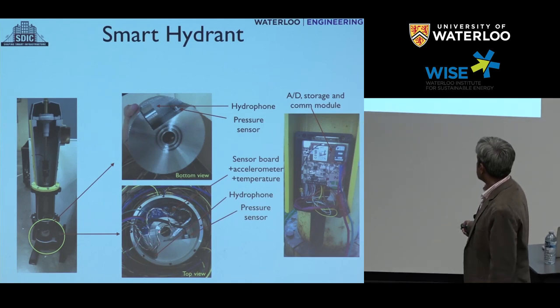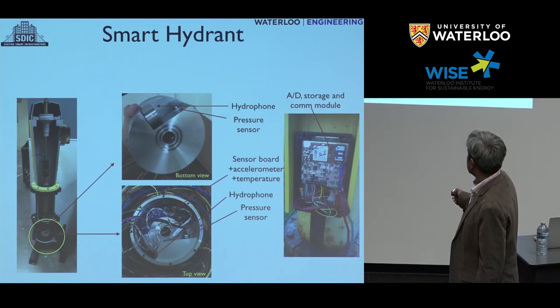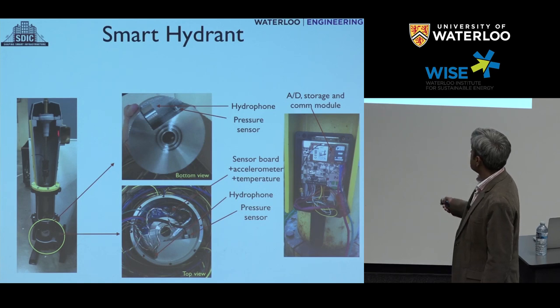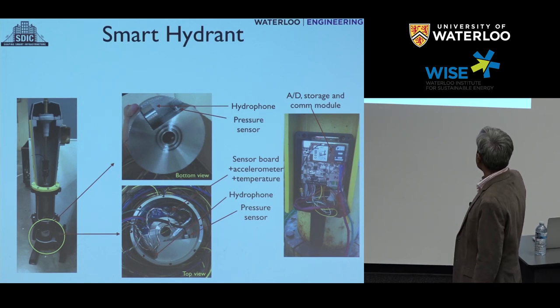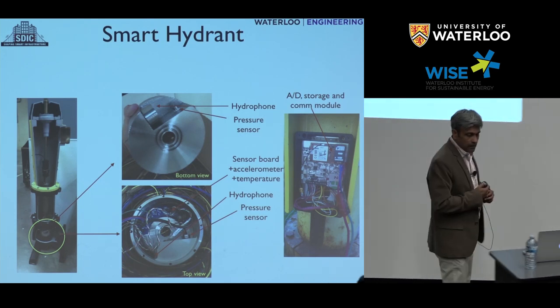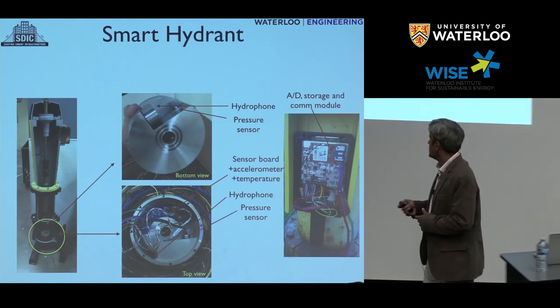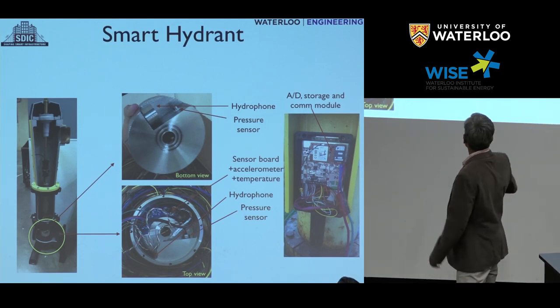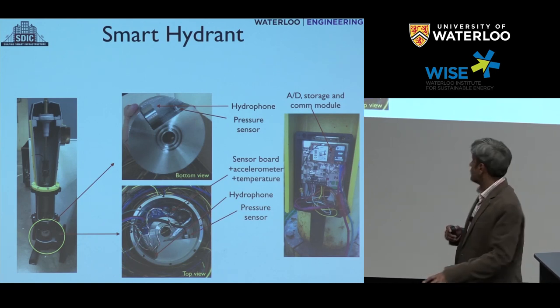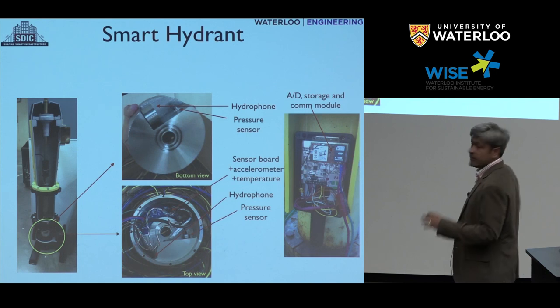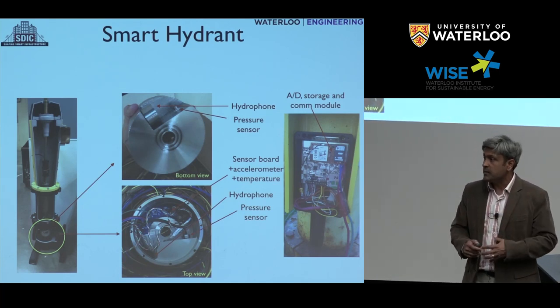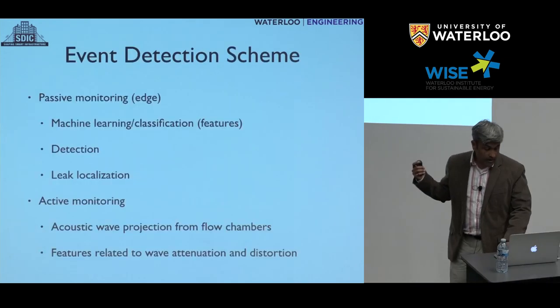Here are pictures of our hydrant in the hydraulics lab. The two sensors you can readily see are the hydrophone and the pressure sensor; there's also an accelerometer and temperature gauge. This gives a multi-sensor modality. The data is collected within the system and hauled back into the data acquisition unit — we now have a very latest version with GPS and cellular connectivity. You take the data from the hydrant, process it, compress it, including data acquisition on the microcontroller, and then send the feature set out into the cloud. If anything is happening at a local level, alarms get triggered right there at the hydrant. More sophisticated environment models are built using the features in the cloud.